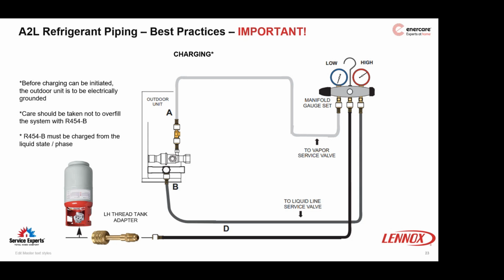Terry, I see you got your hand up. Yes, just going back to the evacuation process, getting under 500 microns is quite easily done with new refrigerant piping and new oil in your vacuum pump. But if you're reusing a line set, God forbid, there was no discussion about flushing the lines. So if it's 410A, are we compatible? Or we did talk about it earlier. I don't know if you missed it.